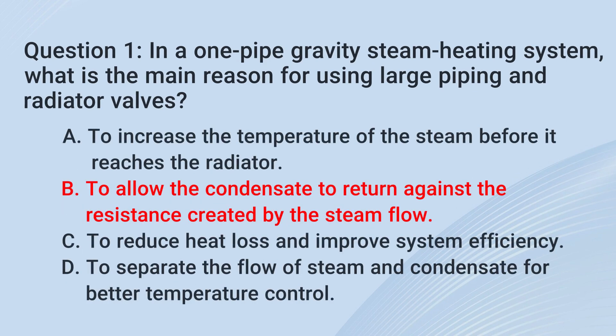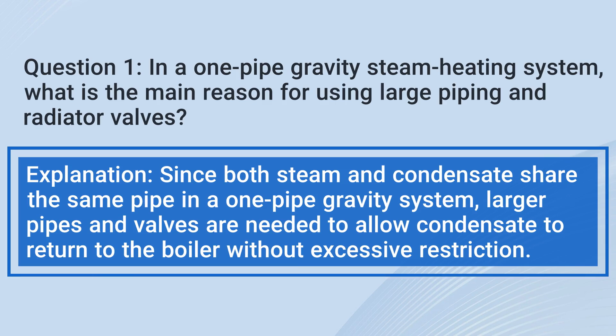The correct answer is B. To allow the condensate to return against the resistance created by the steam flow. Since both steam and condensate share the same pipe in a one-pipe gravity system, larger pipes and valves are needed to allow condensate to return to the boiler without excessive restriction.